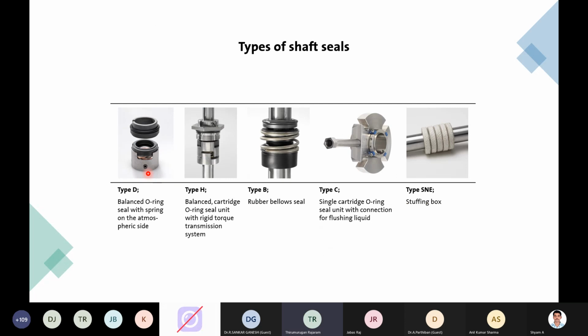So we touch upon the shaft seals. Obviously, you will have a lot of pumps running with shaft seals, and also with gland packing, because in older design pumps, you can find these gland ropes being installed as packing between the sealing of your pump and your shaft area, and there will be a leak, because when you have packing, it is a kind of nylon wire which you need to lubricate with the water, so it will lubricate and it will create a leak. Okay, but if there is wear and tear, there will be excess leak, so that will pollute the surroundings, and that can be a hazard also in terms of the environment itself. So always adopt mechanical seals in all your pumps, because a mechanical seal improves the efficiency of the pump. It will avoid water wastage, and in turn you will have a more efficient pump also.